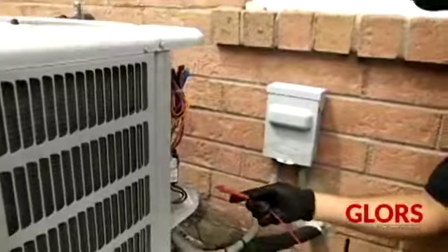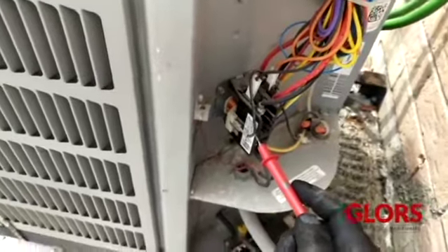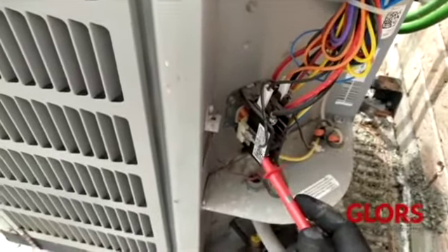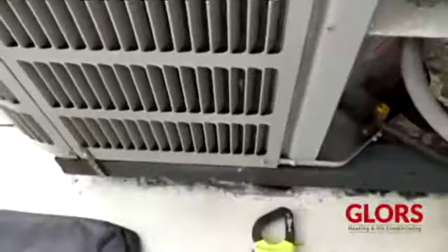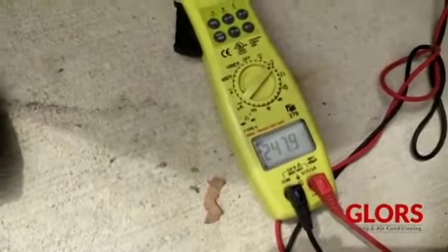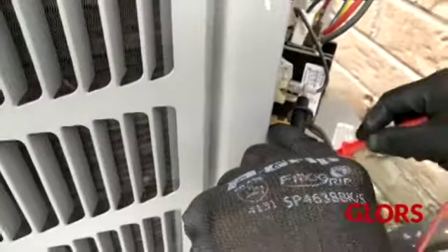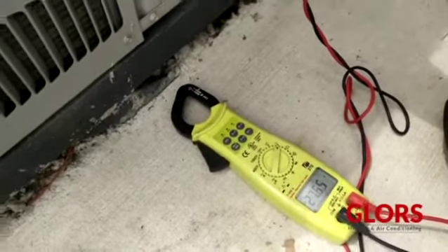Now this is our contactor. Initially it's getting power here, and there is another power coming from your thermostat or from the furnace. This is 24 volts. Let's see, when I put the probes here, I should read 240 somewhere. You can check on my multimeter: it's set to AC voltage, and it's 247, 248, which is fine. It should be like that. Now we are checking the 24 volts, and yes, I'm getting 24 volts. It's actually 27, but we still consider it 24 volts.